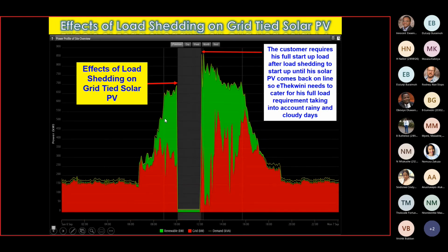So the other problem, as explained previously on this curve, is that before load shedding you've got a portion of the load fed by the PV system and a portion by the grid. But when load shedding comes, everything goes off. Once the grid returns, the PV system will not come back immediately, so the grid needs to feed the customer's startup load etc. and take that up before the PV system can synchronize and come back online.